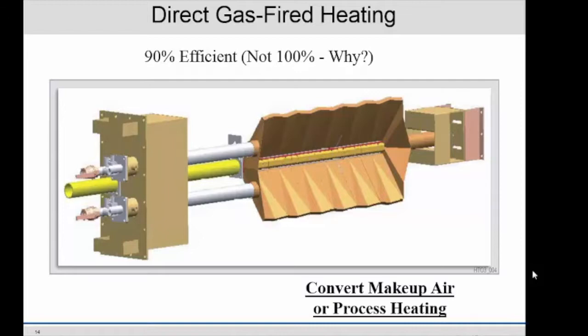Also, it's not 100% efficient. People think because you dump it all into the building, all the energy is in the building. Well, about 10% of the gas is used to make water, the hydrocarbon. You get the hydrogen in the fuel, and the oxygen in the air makes water vapor. So you lose about 10% of your energy just making water vapor. If you're using it in makeup air, it doesn't ever condense, like in a condensing boiler where you can lower the temperature of that flue gas and get that energy back. This doesn't, because the air is really dry. It just sucks up that moisture, so it never condenses back. You never get that energy back.